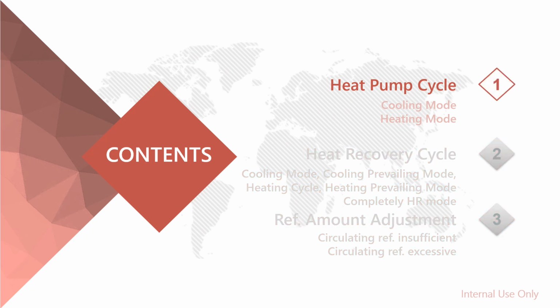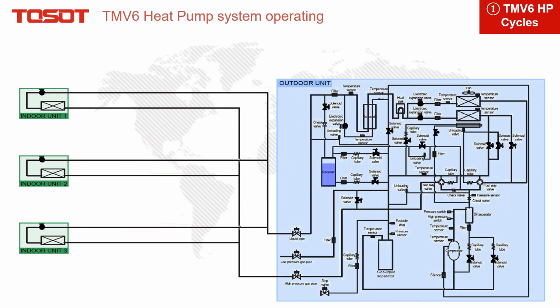Heat pump cycles. In this slide, I just put one outdoor unit connected with three indoor units: 1, 2, 3. First, let's focus on the indoor unit. It is very simple, just the heat exchanger with the EXV, only one. But the outdoor unit is very complicated, right? There are so many components. For the valves, there are three: the liquid valve, the low pressure gas valve, and the high pressure gas valve.